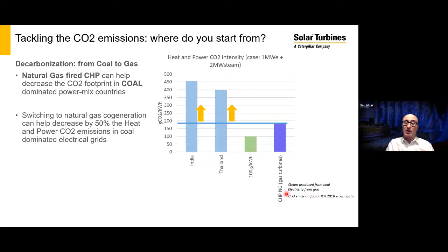The CO2 intensity of this plant will actually be 450 grams of CO2 per kilowatt hour. If you look at this purplish bar, which is a CHP natural gas fired based on a gas turbine, you see that you will be right under 200 grams CO2 per kilowatt hour to produce the same power and heat. So there's a very nice opportunity there for more than 50% improvement in CO2 footprint moving to natural gas fired CHP. It's a very interesting opportunity.